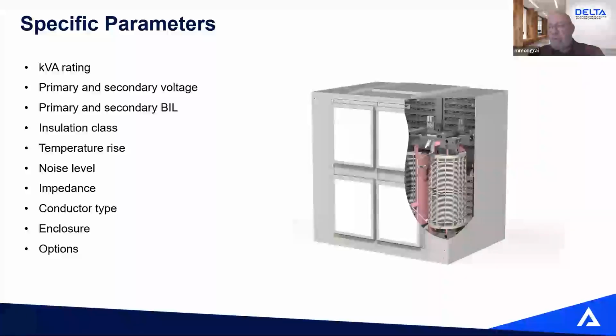The impedance, usually when we replace or retrofit, and if you keep all of the low voltage switchgear, we want to match the existing transformer impedance so that your fault current and downstream breakers are still compatible.